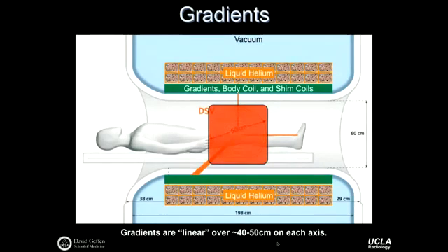And that means that all of our hardware is focused to have ideal operating characteristics at isocenter within plus minus 25 centimeters or something like that. So we can't really do imaging experiments of the chest with a person's head sitting out of the scanner. And if their knee is at isocenter, we also can't really image their foot. There are limits, despite the overall size of the scanner, to the effective area where we can encode information and excite spins with the hardware.